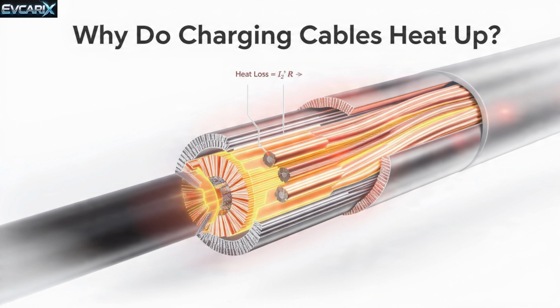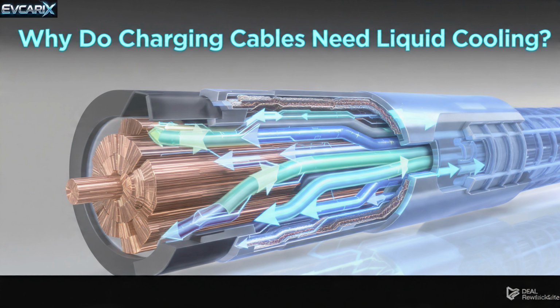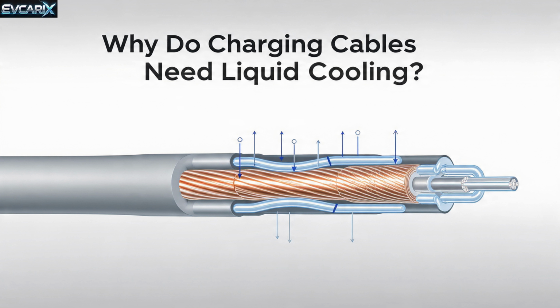This isn't just about efficiency. Faster heat means larger cooling systems, heavier cables, and shorter component life. In a 400 volt system, once cable heat becomes difficult to manage, the charger reduces power, and you keep waiting at the station. That's why understanding charging speed starts with understanding heat. Let's go deeper into this heat issue. Passive, air-cooled DC cables in practice approach their thermal limit around the 200 to 300 amp range. Operating continuously above that level is not sustainable in proper designs.